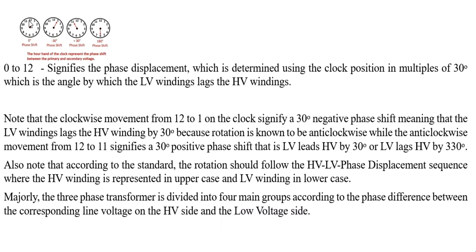We are going to be using the clock sign. Look at the screen — you can see 12 o'clock, 1 o'clock, 11 o'clock, and 6 o'clock. When it is at 12 o'clock, the phase shift is zero, meaning there is no phase shift between the low voltage winding and the high voltage winding. From 12 to 1 is standardly 30 degrees. The total clock symbol represents 360 degrees — from 12 to 1, 1 to 2, each step is 30 degrees, all the way around back to 12, which equals 360.